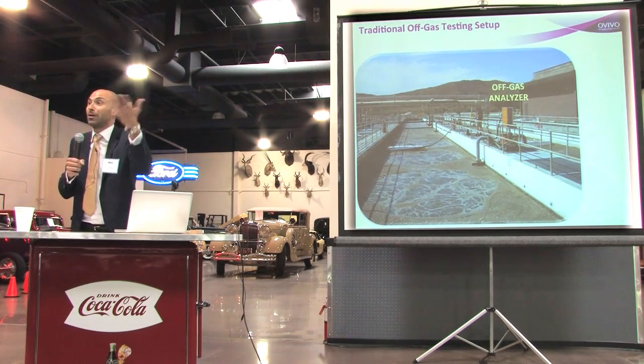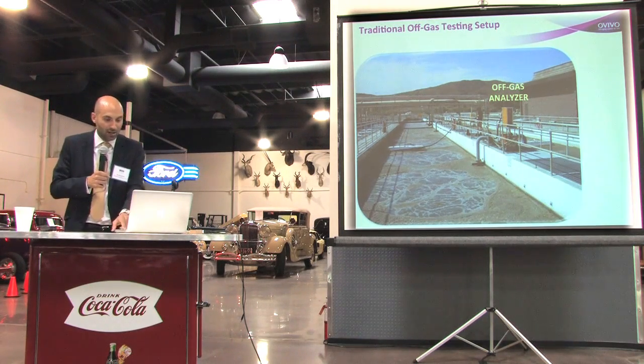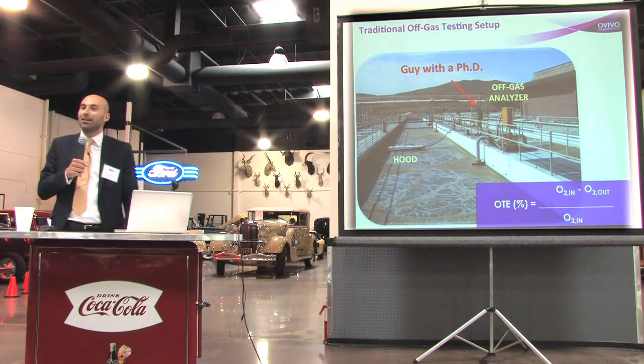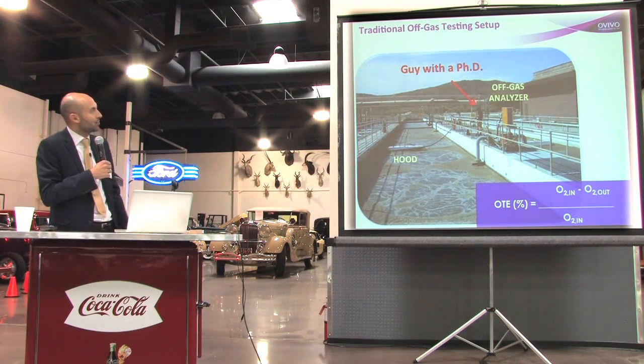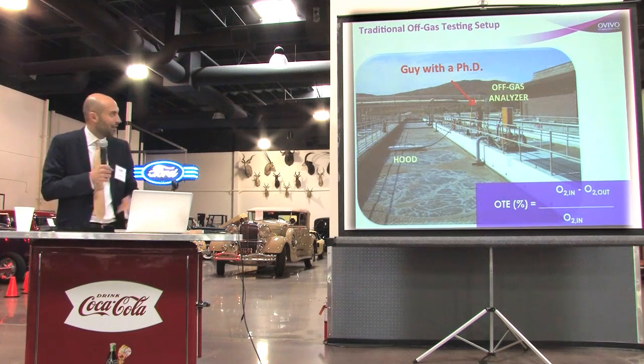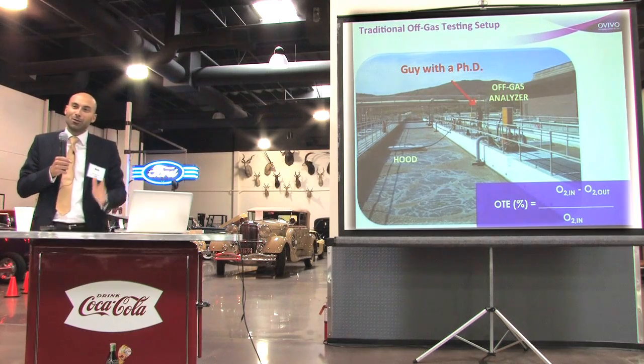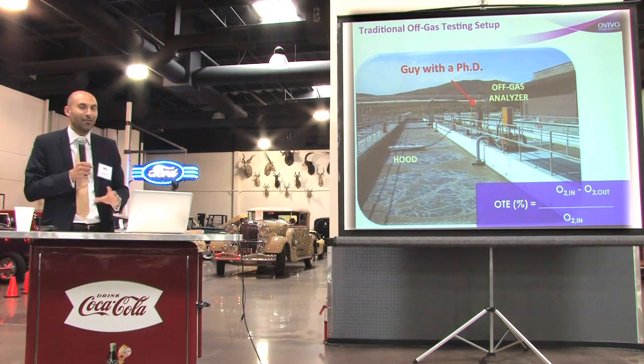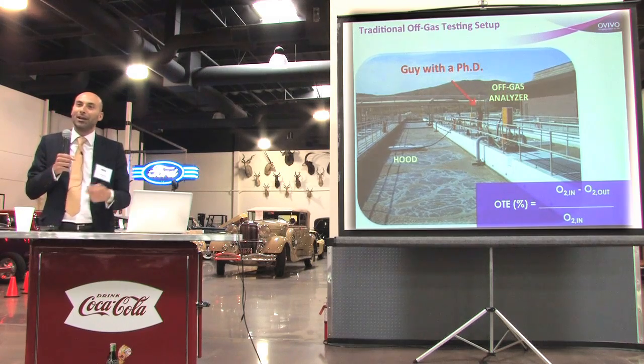Taking flow-weighted average measurements across the tank also gives an efficiency profile — closer to the head of the tank you need more diffusers because oxygen demand is higher; at the outlet, demand is lower as most has been resolved. The traditional setup uses an off-gas analyzer, a hood, and a PhD-level person doing the analysis. The old analyzer was manual and the hood was very heavy — I was always tasked with lifting it as a student — which motivated me to build an automated system.